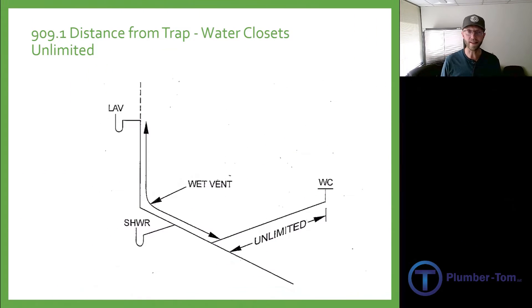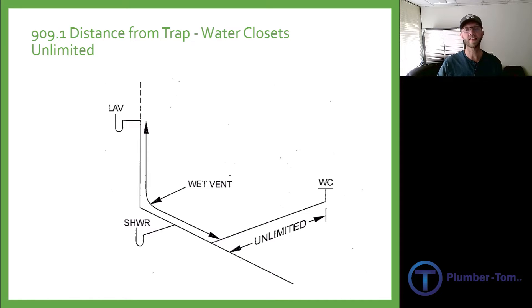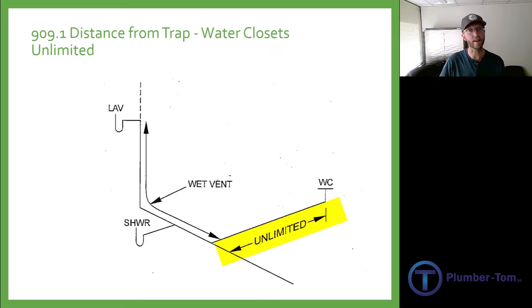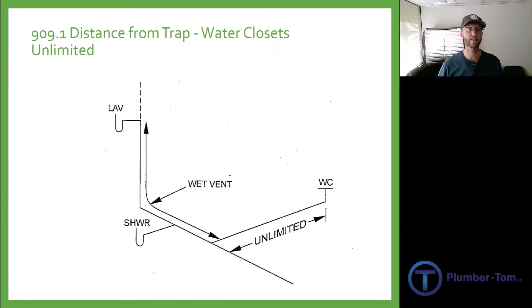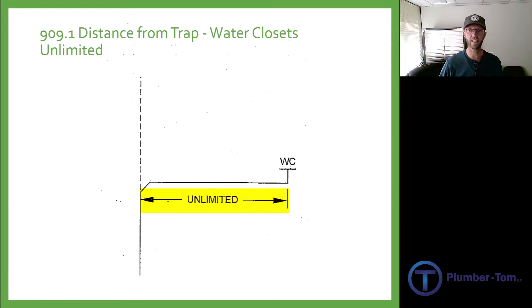Important note on toilets: they do have to connect to a vent. Here we have a toilet connected to a wet vent. But there is no limit to the distance for a self-siphoning and self-refilling fixture like a toilet — it will refill its trap seal every time. So no limit. Here we have a stack with stack vents and a toilet connected — no limit to the distance.